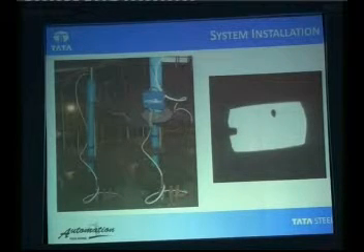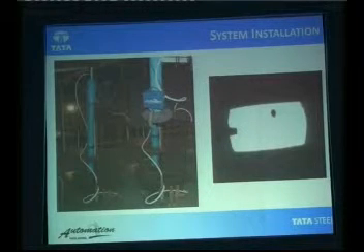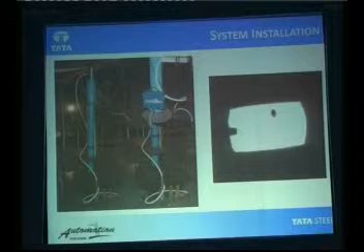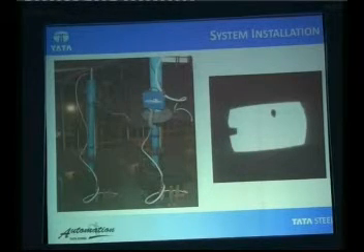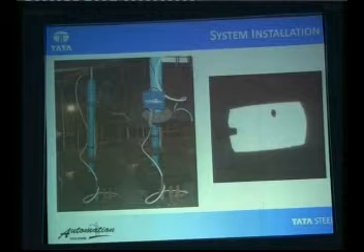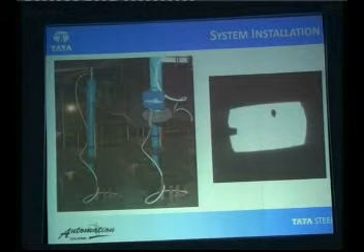The next issue was that, with temperature and moisture condensation taken care of, we had to cool the camera itself because the electronics produce a lot of heat. For that we have an air purging system for this tube. Since the measuring house is about 6 meters away from the rolling bed itself, we had to take care of only the tube. Continuous air is purged through the pinhole, and another advantage is that we create a positive pressure at the pinhole, so the dust from outside never comes inside.